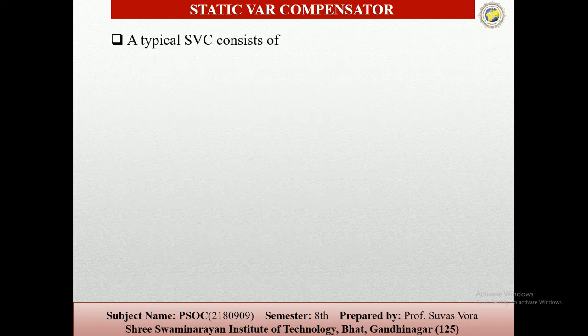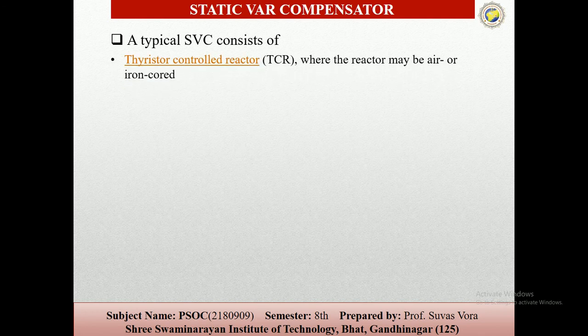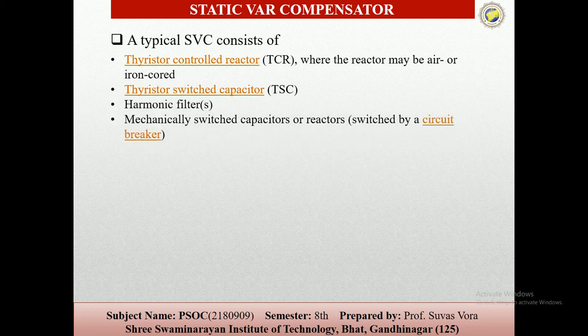So the typical SVC consists of the thyristor controlled reactors, TCR, where the reactor may be air or iron cored, then thyristor switched capacitors, TSC, then the harmonic filters, and mechanically switched capacitors or reactors.